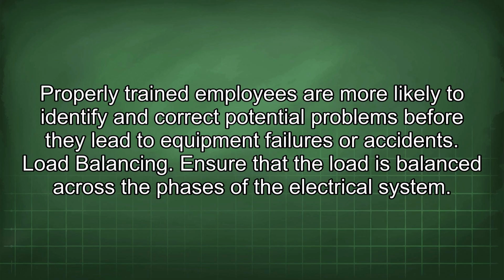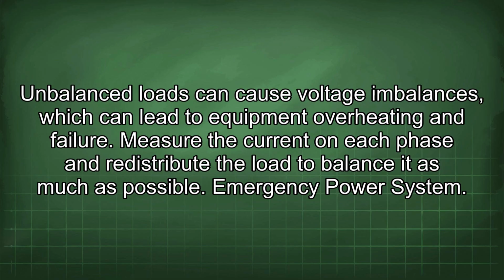Ensure that the load is balanced across the phases of the electrical system. Imbalanced loads can cause voltage imbalances, which can lead to equipment overheating and failure. Measure the current on each phase and redistribute the load to balance it as much as possible.